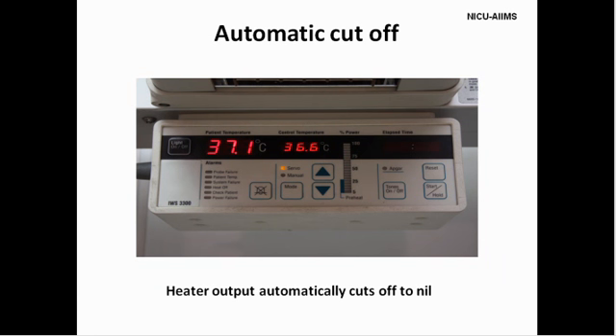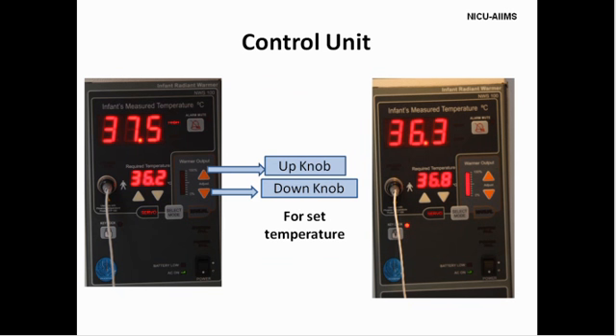As we can see here, the baby's temperature is 37.1 degrees Celsius. The set temperature is 36.6 degrees Celsius, and we can also appreciate that the heater output is nil. Important point to be noted here is that the heater output automatically cuts off if the patient's temperature exceeds the set temperature by 0.5 degrees Celsius. We can adjust the set temperature by moving the up and the down knobs. Some units in addition have the provision of a lock system, that is, once the settings have been decided, these settings can be locked so that inadvertent change is not possible.